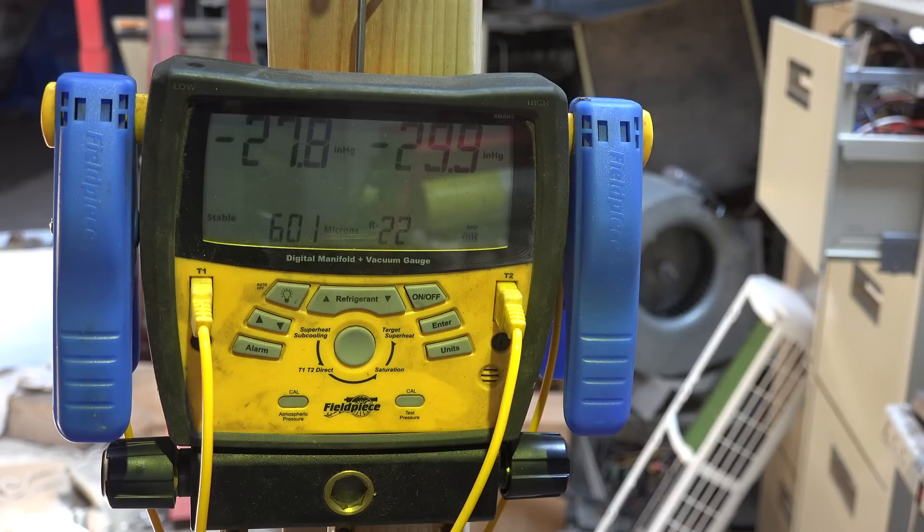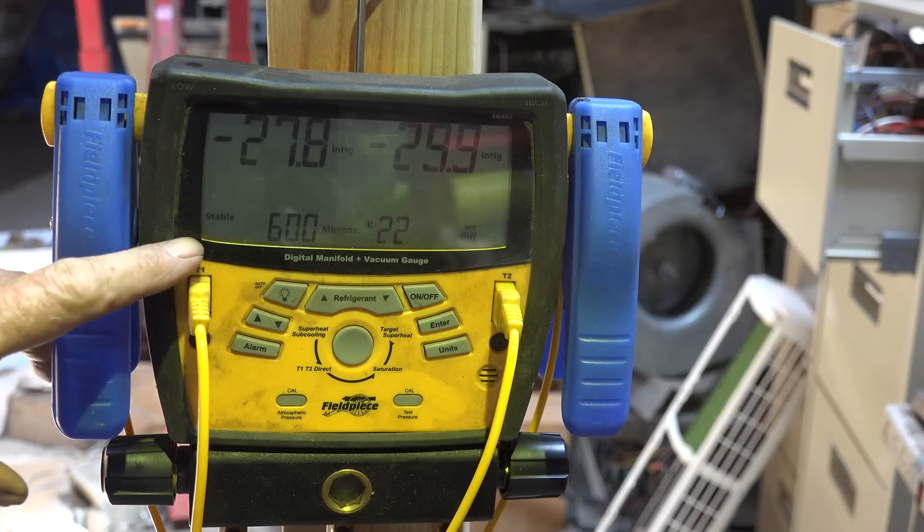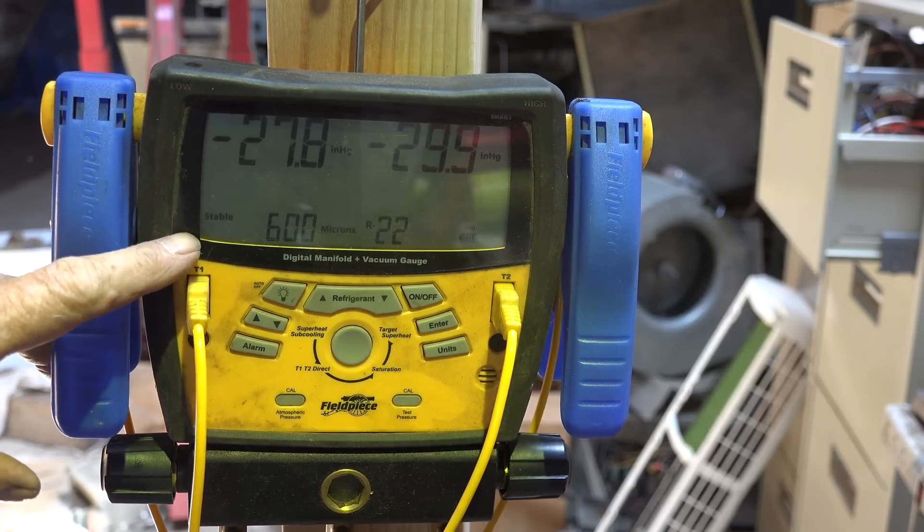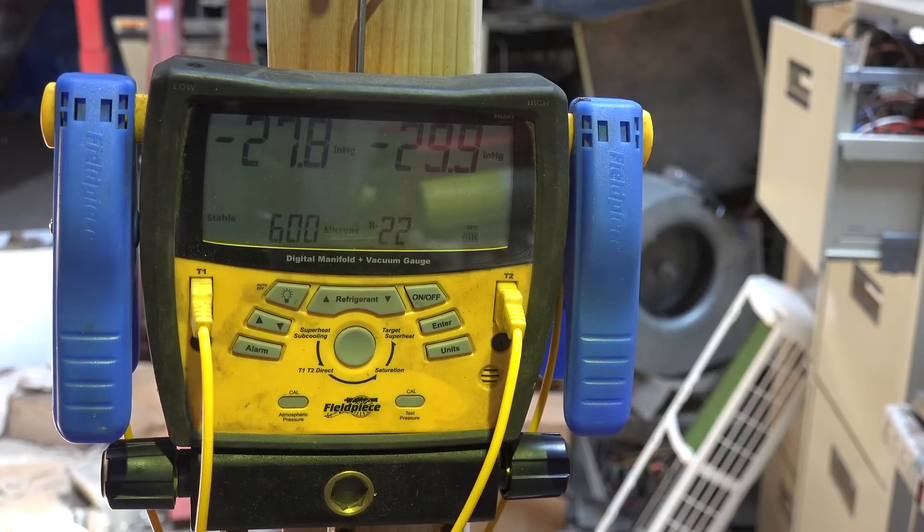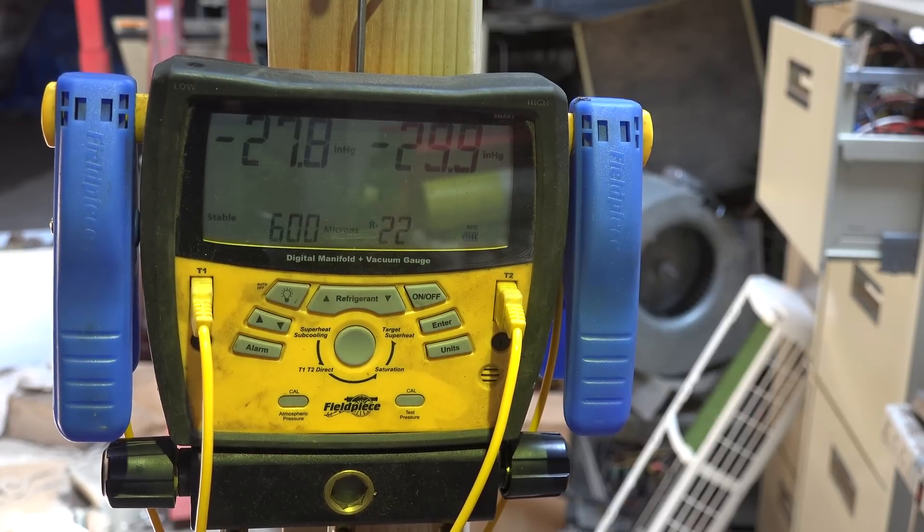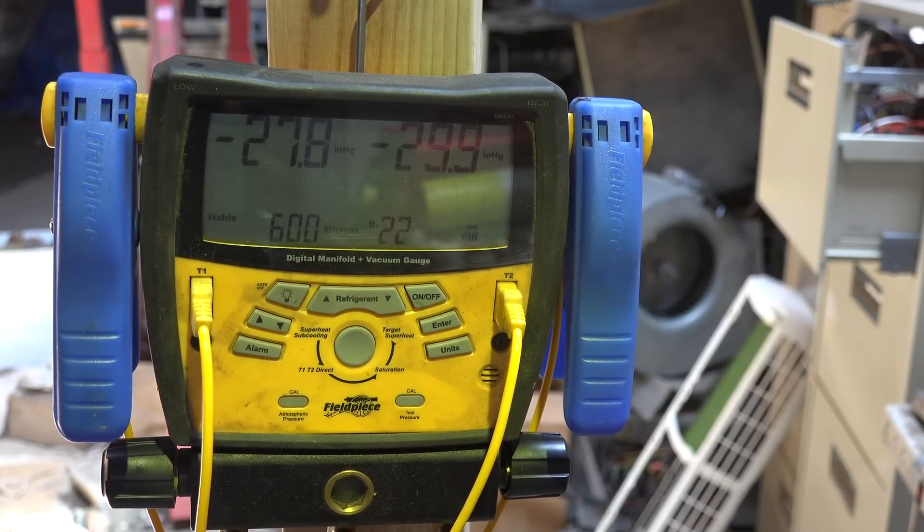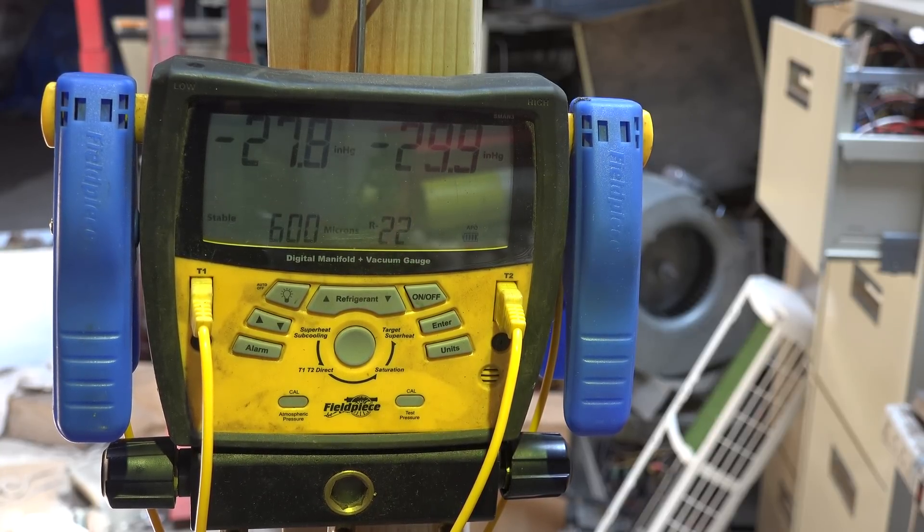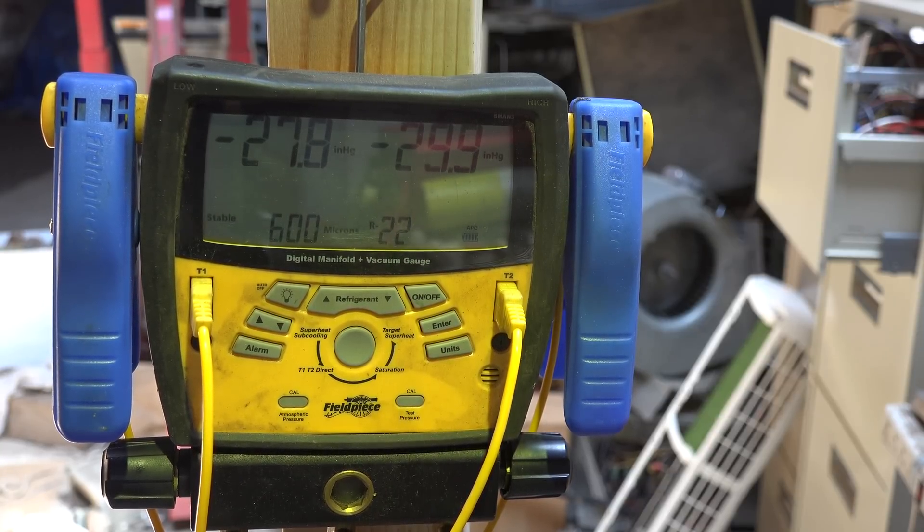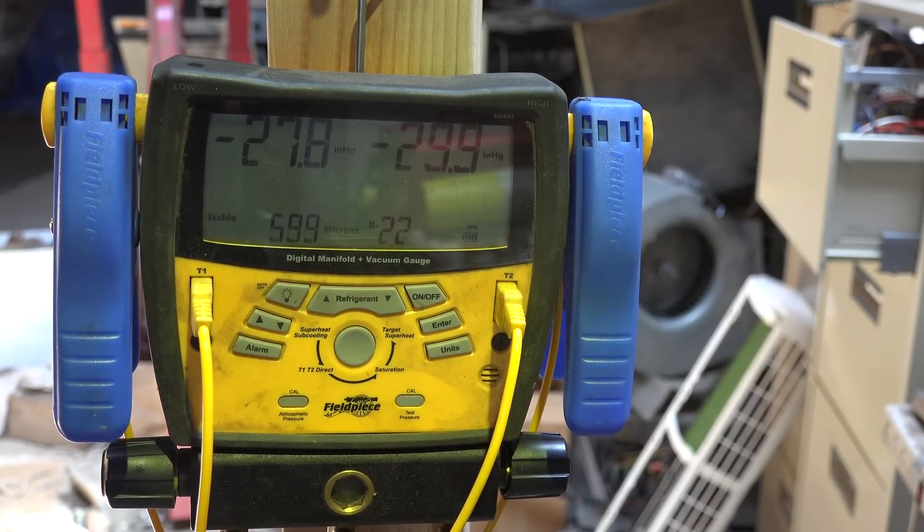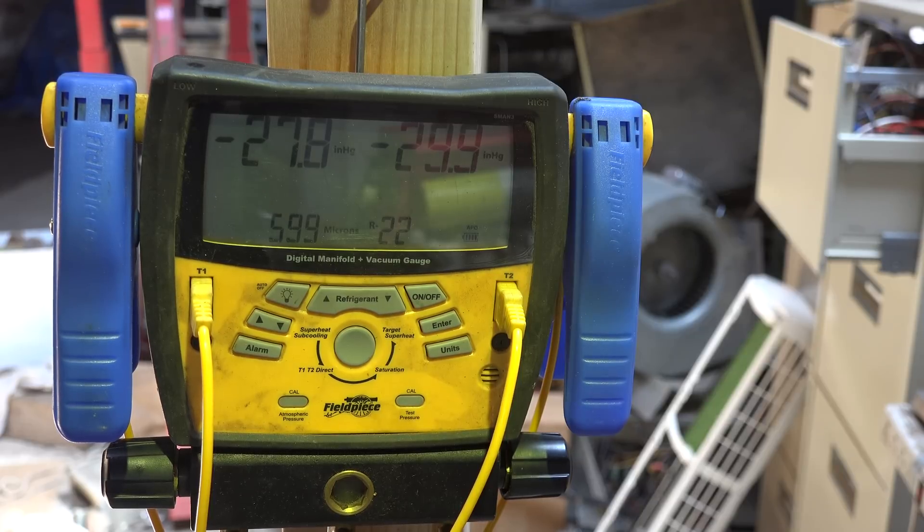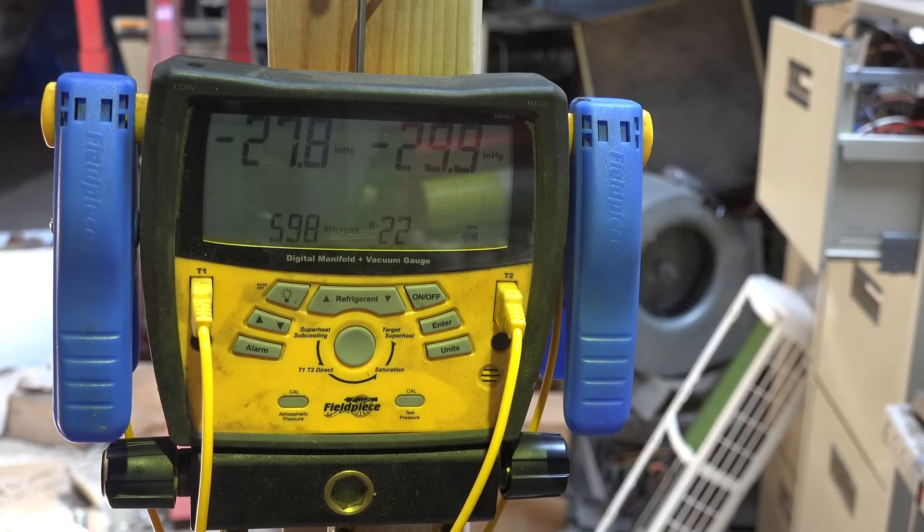Now you can see here it's showing stable. It's probably going to drop to 599 or so pretty soon. It's pretty close to a deep vacuum, but it doesn't seem to want to go much below what it is right now.